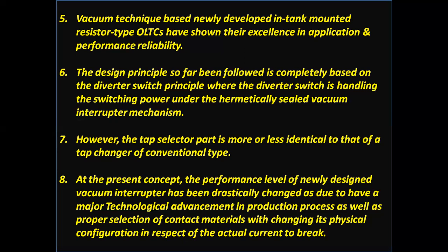In the present concept, the performance level of the newly designed vacuum interrupter has been drastically changed due to a major technological advancement in the production process as well as proper selection of contact materials, with changes to its physical configuration in respect of the actual current to break.